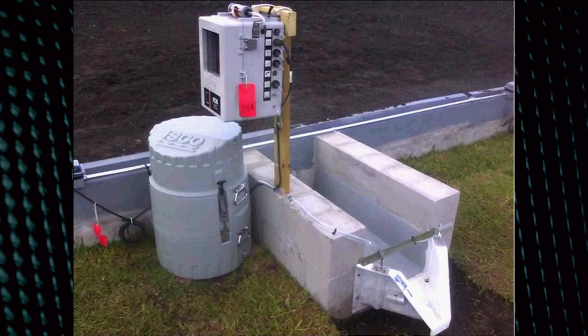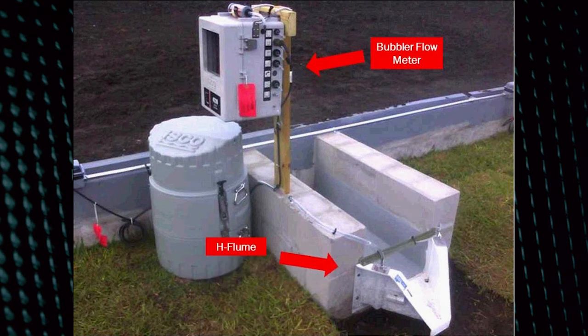Here's an application of an agricultural runoff field. They channeled it around so all of the runoff would come out of these H flumes. They've added a bubbler flow meter connected up to the H flume so that you can monitor the flow. Also connected is the automatic sampler, which is triggered by the flow meter. When a storm happens and runoff flows off the field, as soon as the bubbler flow meter notices the water rises, it activates the sampler. They use an H flume because the water flow is very slow and very low, giving good accuracy at really low levels.